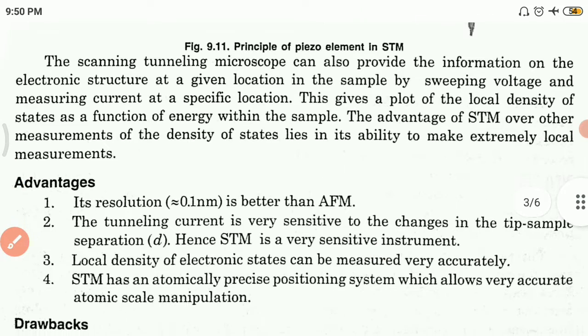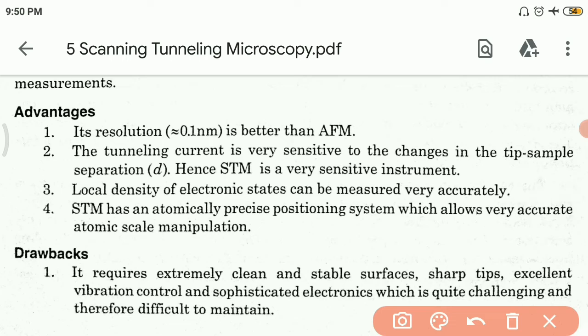Further advantages are noted here point-wise. Number one, as we have seen, it has a very high resolution. Its resolution is around 0.1 nanometer, which is much better than the atomic force microscope, that is AFM. Number two, the tunneling current is very sensitive to changes in the tip-sample separation, that is small d. So if we change the value of small d slightly, it can affect the tunneling current. Hence, the STM is a very sensitive instrument. Number three, the local density of electronic states can be measured very accurately by this STM. Then in the fourth point, the STM has an atomically precise positioning system which allows very accurate atomic scale manipulation.